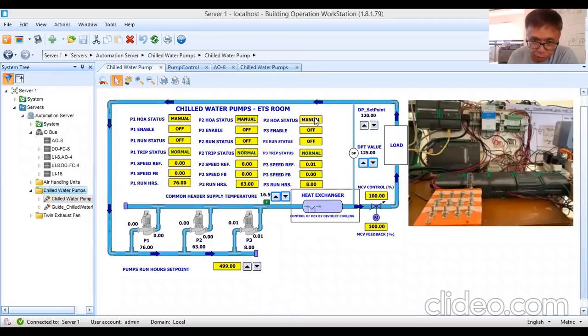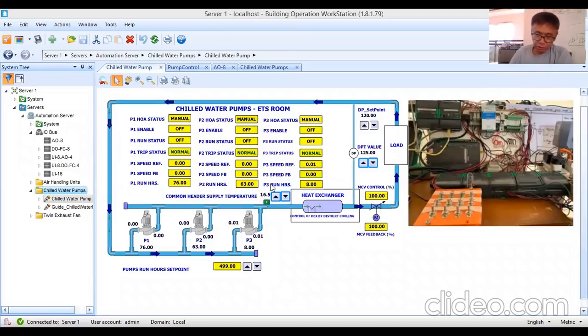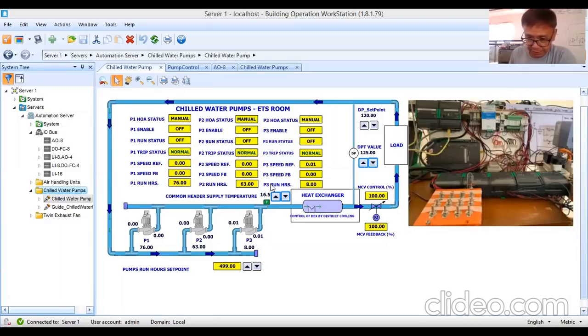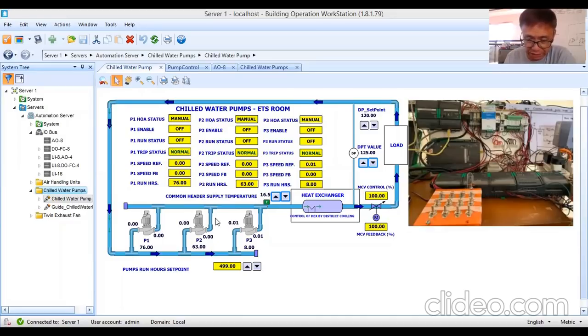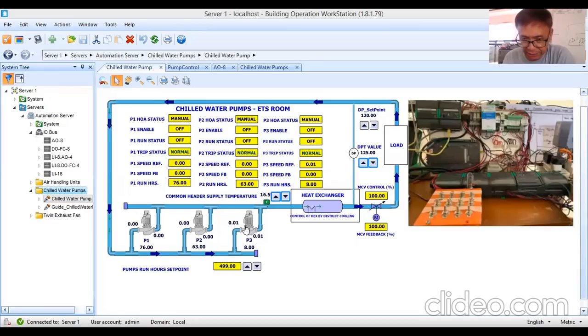Today I'm going to show you how to test or simulate the operation of these three pumps based on a very simple sequence of operation. The sequence of operation should be given by the designer or the consultant. Since I don't have one provided, I've prepared a simple one. The sequence is: two pumps will always run when the system is in operation — pump one and pump two are duty pumps.